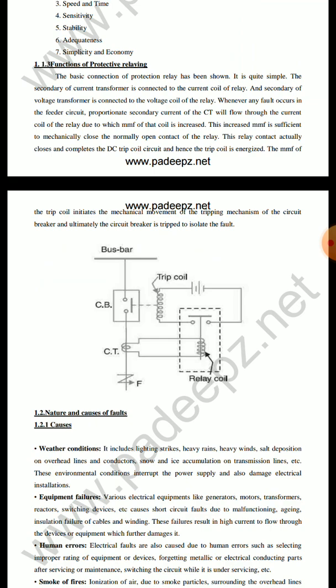Here one current transformer is connected. When a fault occurs, this current transformer's current value may vary. Because of that, the variation will energize the relay coil, and this will activate the trip coil, and that trip coil will operate the circuit breaker. The circuit breaker is used to break the entire circuit. It is used in various categories, because circuit breakers are available based on usage. Maybe generator oriented, or bus bar oriented, or transmission line oriented.